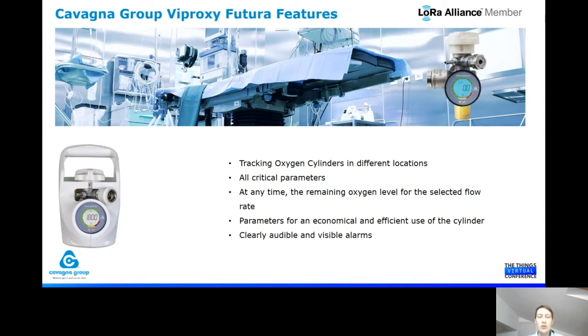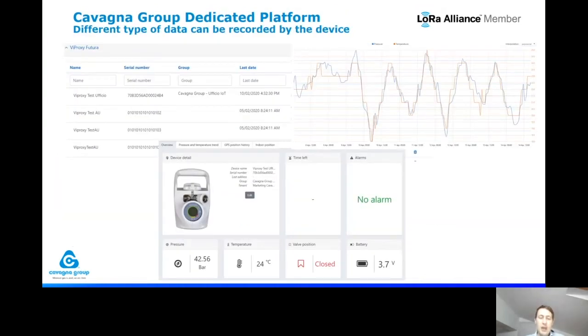This reduces the risk of losing cylinders, having cylinders that are unused, or cylinders going empty with no possibility to check them. All alarms are also collected, so we have a history of what happened to that exact patient and how the oxygen cylinder was used. All data are collected to the Cavagna Group cloud platform, where we show different information according to what is needed — we track the pressure, temperature, time, valve position (closed or open), any alarms, and we can always see the time left.